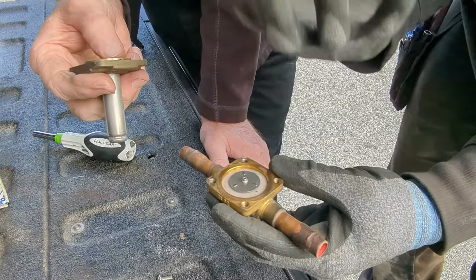Well, we actually got a call back to one of them because we didn't realize we removed a lot of fluff and debris that day. We swept it away and took it away, but we didn't realize some of the dust had gotten trapped inside the condensate drain, and that was completely clogged up.